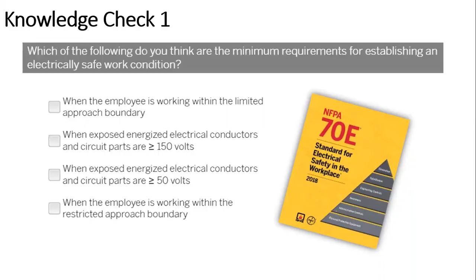It's first and third. What is this limited approach boundary? If I go back to this slide, the limited approach boundary is the boundary from your energized equipment, which can be in millimeters or meters, at which a shock hazard exists. And the restricted approach boundary is the boundary in which there is an increased likelihood of electrical shock. So what's the difference between these two? The limited approach boundary is basically made for people to distinguish between a qualified person and an unqualified person. A non-qualified person will not be allowed to enter this limited approach boundary.